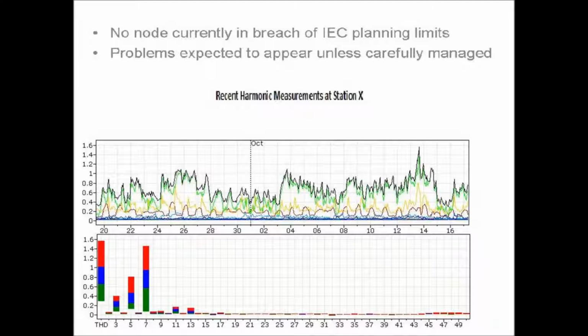The THD, as you can see, never gets below 0.3%. There's always something there. And for the most part, we're in good shape. So the 95th percentile, remember, is where the IEC specifies to, and we stay below 1 on the THD. And the THD for IEC is 3, is what you're allowed to. So even if we were to go from the 95th to the 100th percentile, the most we get to is about 1.5. So we're about halfway there.